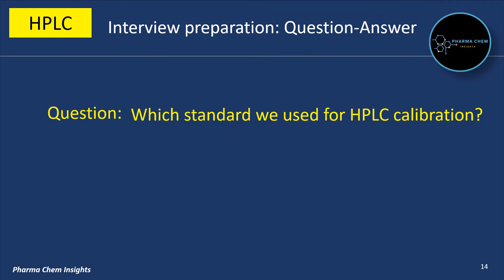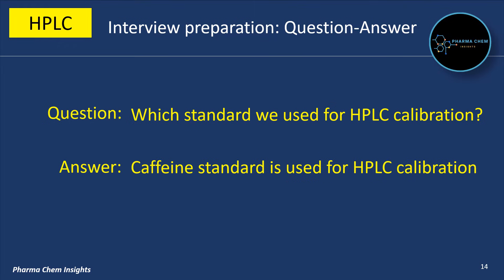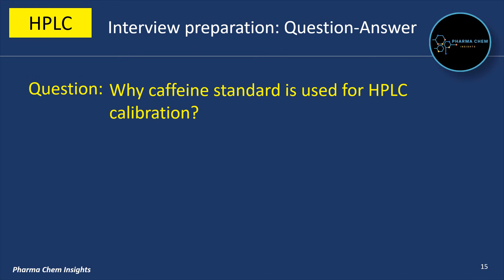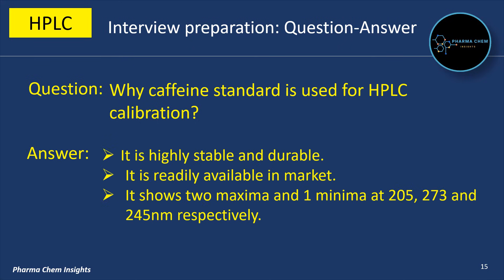Which standard is used for HPLC calibration? Caffeine standard is used for HPLC calibration. It is highly stable and durable, and readily available in the market. It shows two maxima and one minima at 205, 273, and 245 nanometers respectively.